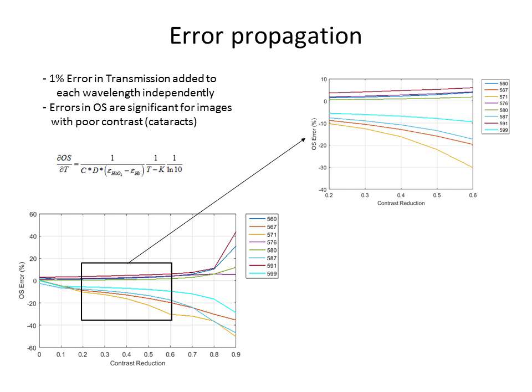Doing some analysis of the model in terms of error propagation, we can predict how it will behave, which will be quite useful once I show you the results later. We added a 1% error in transmission to each wavelength independently, and then we solved the model trying to retrieve the oxygen saturation. Here you can see, for a range of contrast reductions from 0 to 0.9, the oxygen saturation error. You can see some of the wavelengths don't have much oxygen saturation error, but some of the others are quite huge, actually.